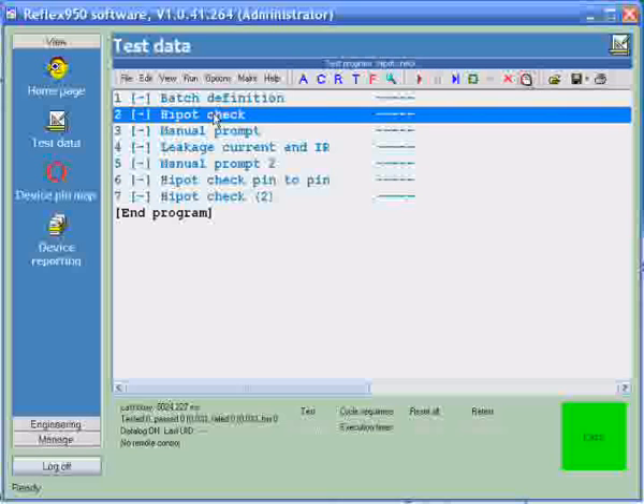If I open up the hipot test, we can see the typical hipot conditions you would expect: the voltage that will be applied, 1500 volts, the dwell time of 0.3 of a second, and some other conditions that we can also edit.